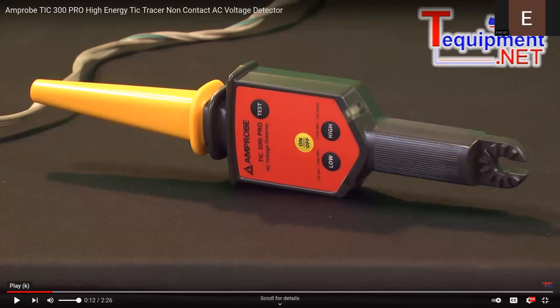Make sure it's de-energized. Take the fuse out. Yeah. A lot of people kind of leave that out: hey, don't work on that until you ground it. Well, my saying is, don't work on that until you test it and ground it. Test it before grounding it. Because if you skip the test part, and for some reason that line is energized and you go to ground it, you're going to have a lot of fire in your face. Test it, then ground it.